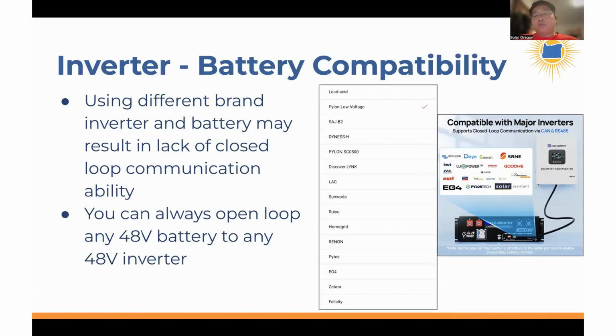Where you absolutely do need closed loop communication is if you want to do things like arbitrage — for example, on an average day while still connected to the grid, using 70% of the battery state of charge, then once it discharges to 30%, having the inverter hop back onto the grid to power the house, leaving that remaining 30% in case of an unexpected power outage. Or maybe instead of 70/30 you want 50/50. If you want to set these precise percentage thresholds for that kind of logic, you absolutely need closed loop communication.